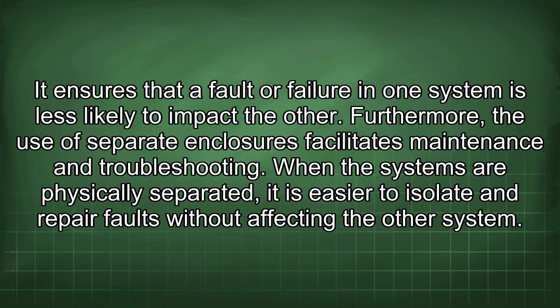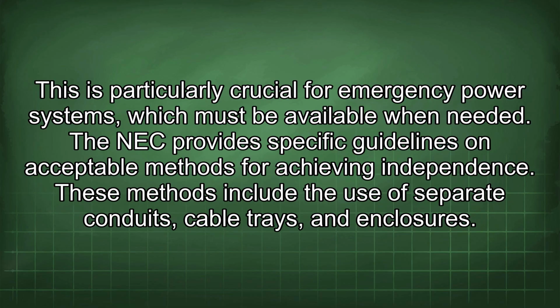Furthermore, the use of separate enclosures facilitates maintenance and troubleshooting. When the systems are physically separated, it is easier to isolate and repair faults without affecting the other system. This is particularly crucial for emergency power systems, which must be available when needed. The NEC provides specific guidelines on acceptable methods for achieving independence. These methods include the use of separate conduits, cable trays, and enclosures.